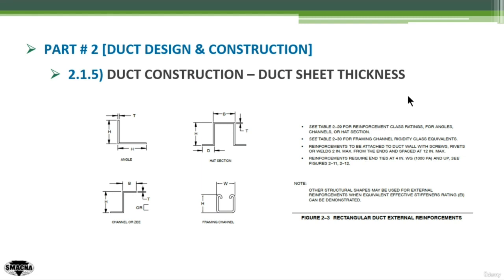You can also see the rigidity class and all the details on these tables from SMACNA. There is a note mentioned in SMACNA that other structural shapes may be used for external reinforcement when equivalent effective stiffness rated EI can be demonstrated. There are also notes at the top right of the screen: see Table 2-29 for reinforcement class rating for angles, channels, or hat sections; see Table 2-30 for framing channel rigidity class equivalents. Reinforcements are to be attached to duct wall with screws, rivets, or welds — 2 inches maximum from the ends and spaced at 12 inches maximum. Reinforcements require end ties at 4-inch water gauge or 1000 Pa and above.